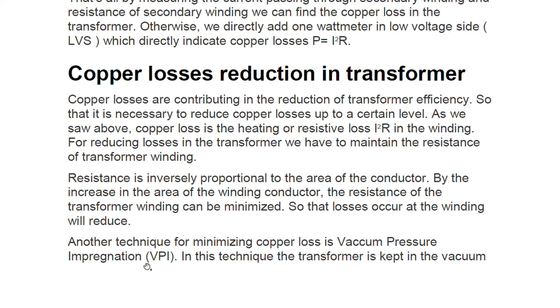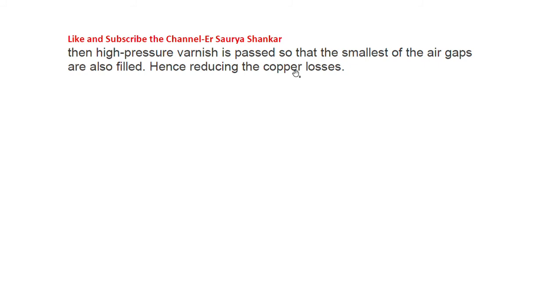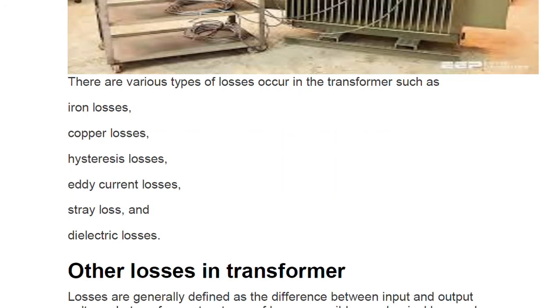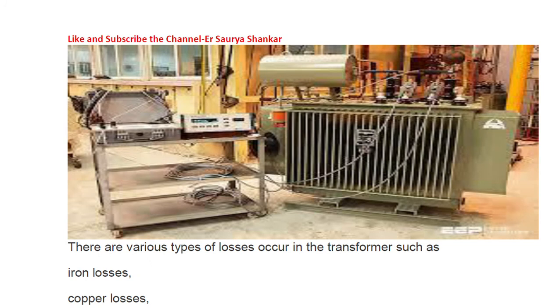Another technique for minimizing copper loss is Vacuum Pressure Impregnation (VPI). In this technique, the transformer is kept in vacuum, then high-pressure varnish is applied so that even the smallest air gaps are filled, reducing copper losses. This is why varnish is used — to fill these air gaps, among other reasons. So there are two methods: increasing conductor area to reduce resistance, and winding varnish application to fill gaps.